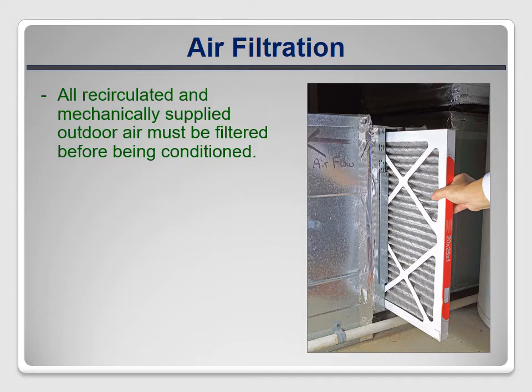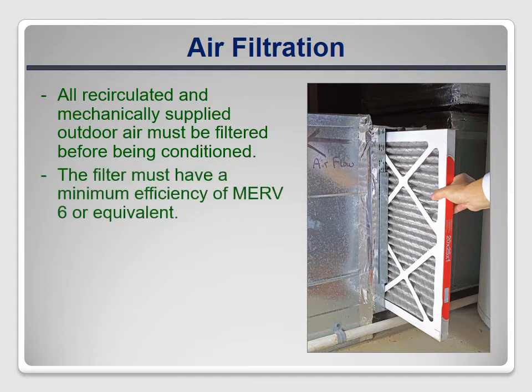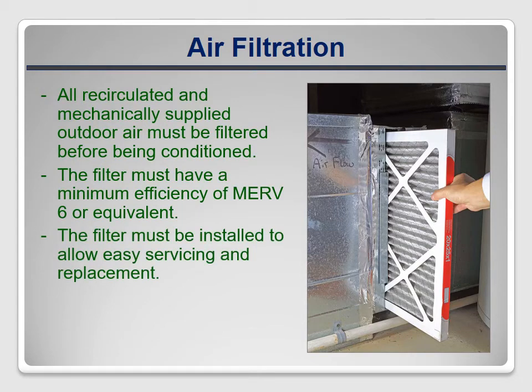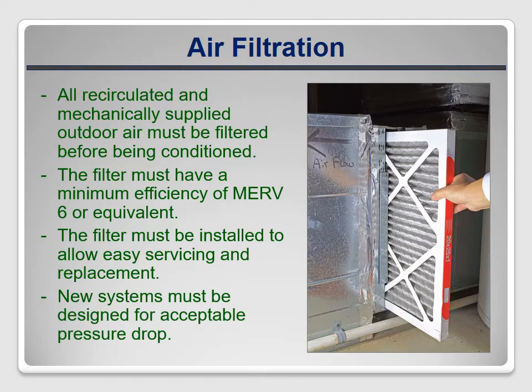The filter must be MERV 6 or tighter and be easily serviced and replaced. It must also be designed with a pressure drop low enough to ensure adequate system airflow.